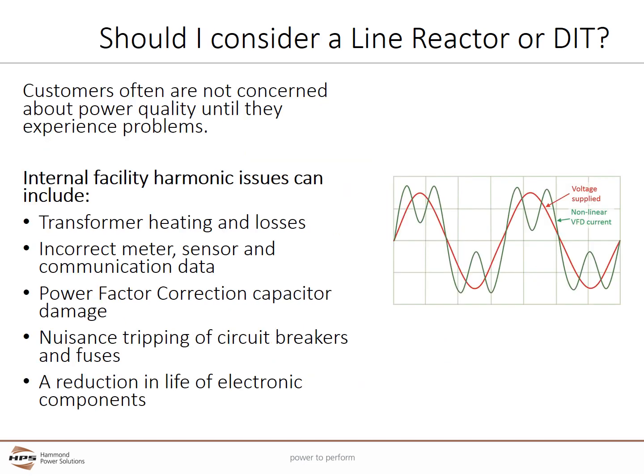Customers are often not concerned about power quality until they actually experience problems. If any of these problems are occurring within a facility, it may indicate line reactors or DITs are needed. Note that other issues can cause these problems, but adding line reactors or DITs is often one of the first solutions to be considered, especially if VFDs are a major power load.